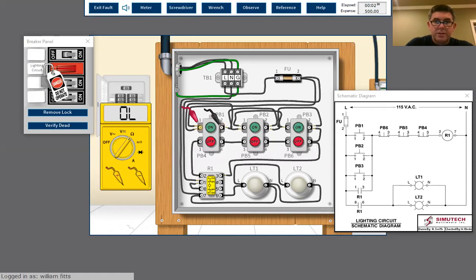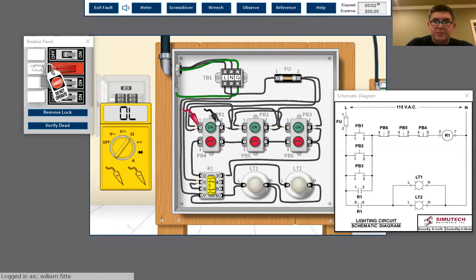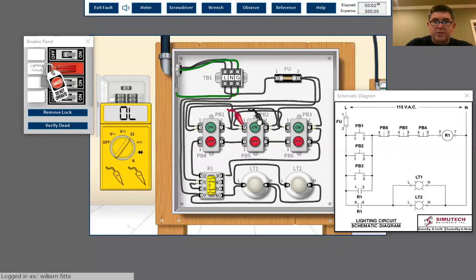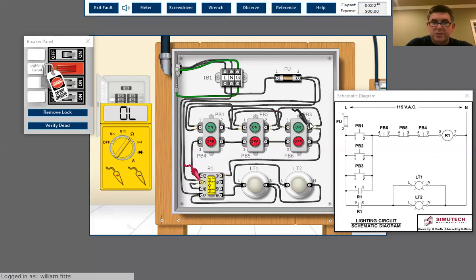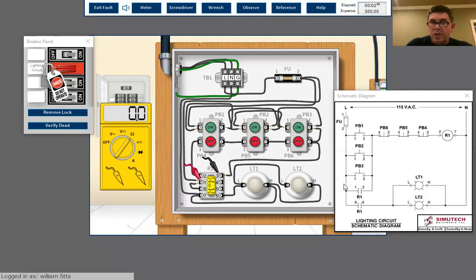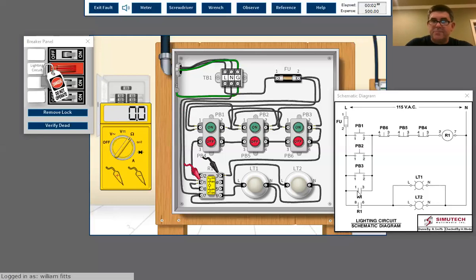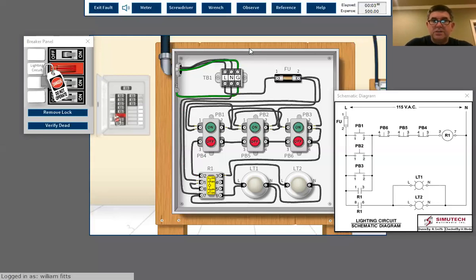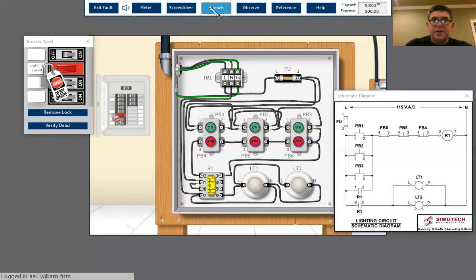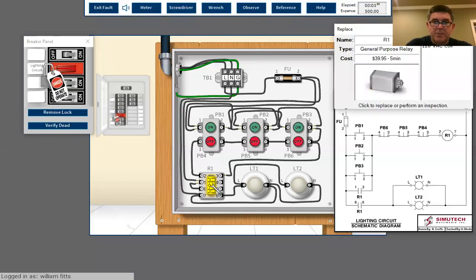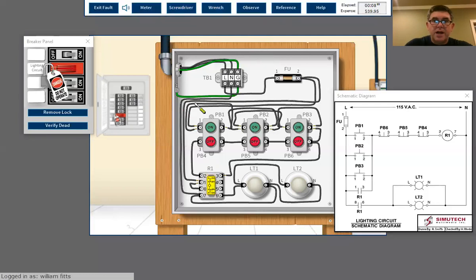If it's open it's OL, if it's closed it's zero. Go to the next one - open and closed, that's working right. That one's working right. Now to me, I bet this one is zero between 1 and 3. Yep, look at that. Between 1 and 3 it's zero, but it's supposed to be a normally open, which means it should be open when it should be open. So contact's bad, contact shorted.